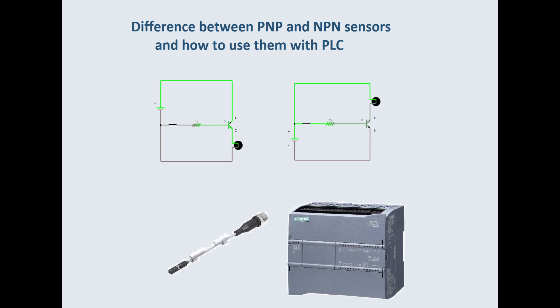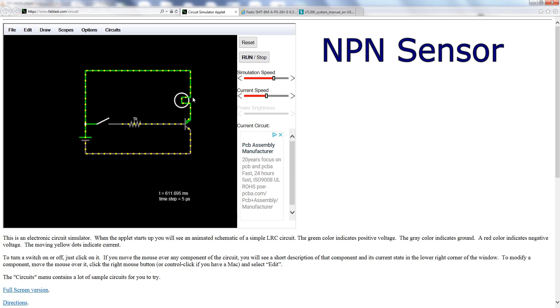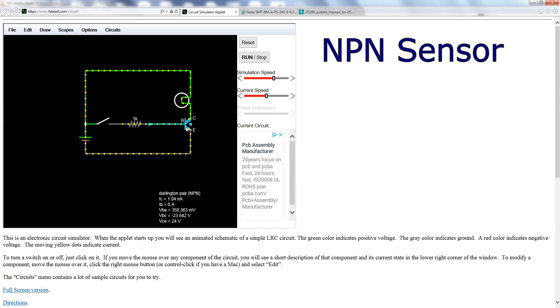Now we can draw the NPN sensor. For NPN, the first letter N means it's switching the negative. The positive is permanently wired to the input, and the NPN transistor is switching the negative — you can see the negative goes to the emitter of the transistor.